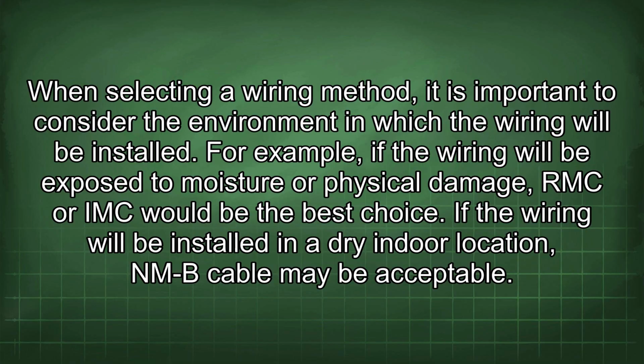When selecting a wiring method, it is important to consider the environment in which the wiring will be installed. For example, if the wiring will be exposed to moisture or physical damage, RMC or IMC would be the best choice. If the wiring will be installed in a dry indoor location, NMB cable may be acceptable.